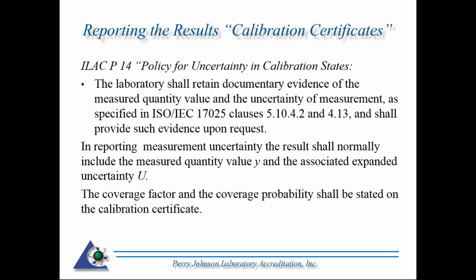Again, this is coming directly from the ILAC P14 document. The laboratory shall retain documentary evidence of the measured quantity value and the uncertainty of the measurement as specified in 17025, 7.8.4.2 and 7.8.4.3, and shall provide such evidence upon request.